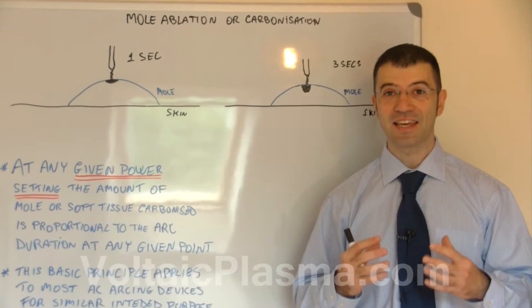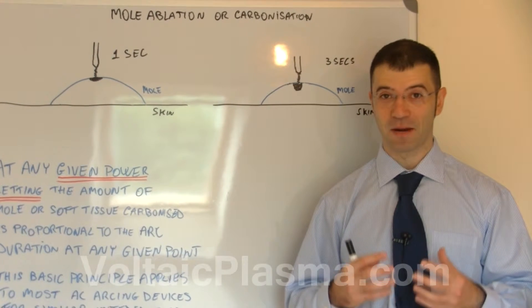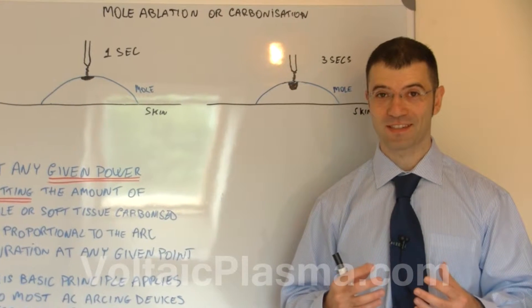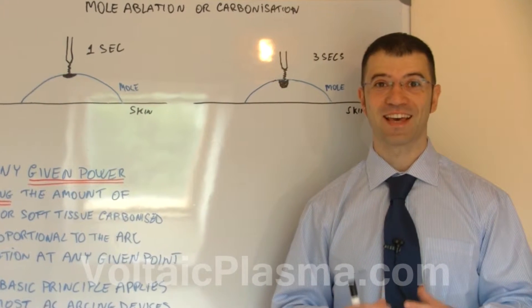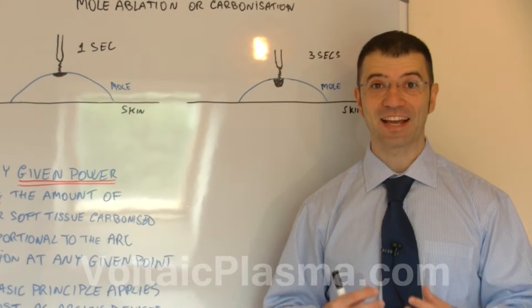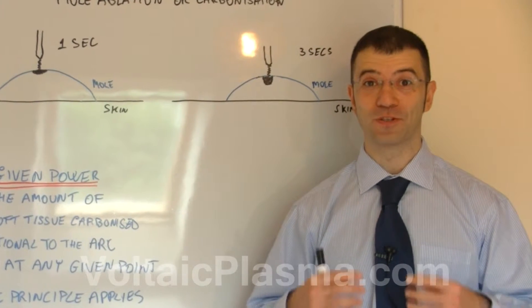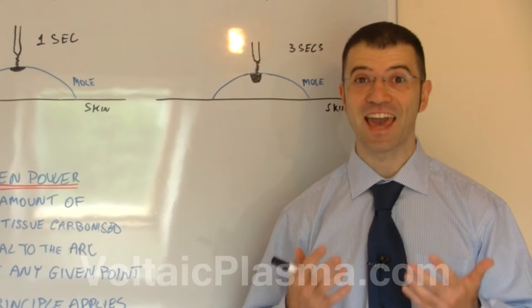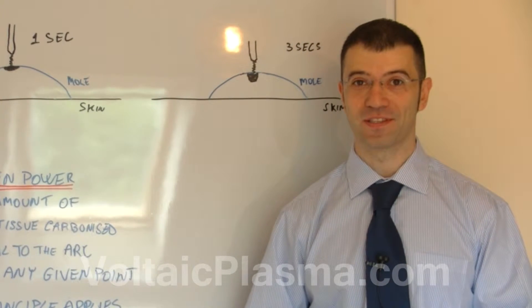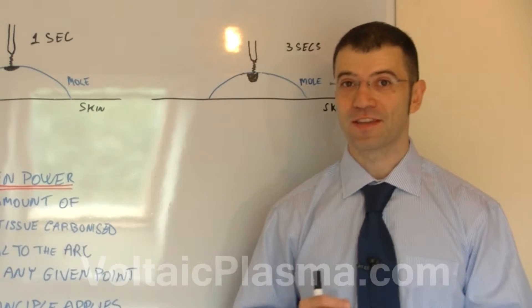At any given power setting, the carbonisation effects or ablation effects are directly proportional to the duration of the arc at any given point.